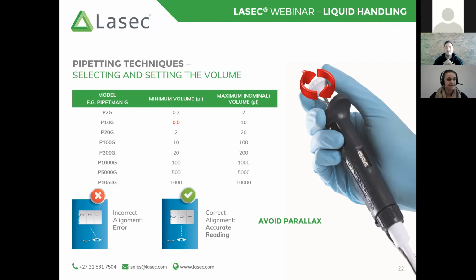Okay, all that simply means Pipetman. So Pipetman is a trademark of Gilson, and that is why all our air displacement pipettes start with Pipetman, followed by a number. That number, in most manufacturer cases, is the nominal or the maximum volume of the pipette. So this is a quick indication to show you this is the maximum amount of liquid I can aspirate with this pipette. It allows you to then decide, can I use this or do I look for a different pipette?